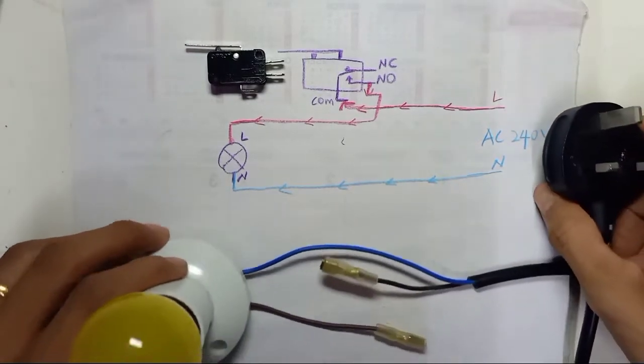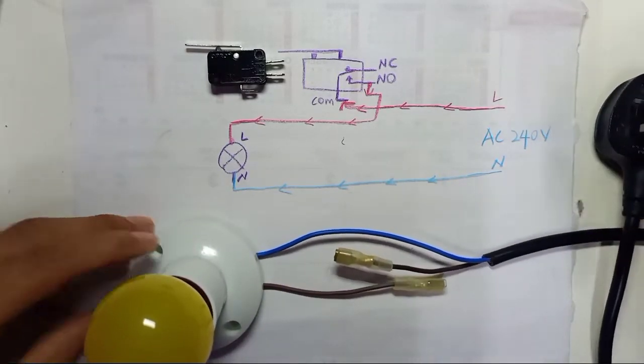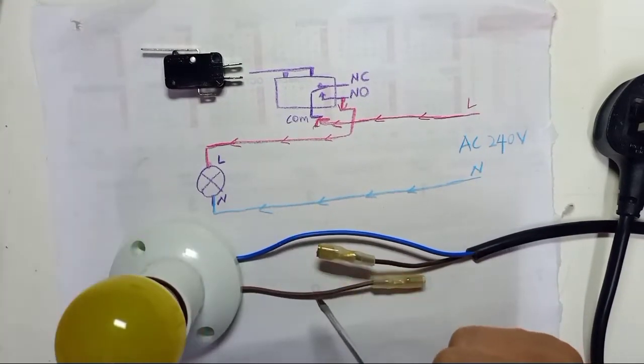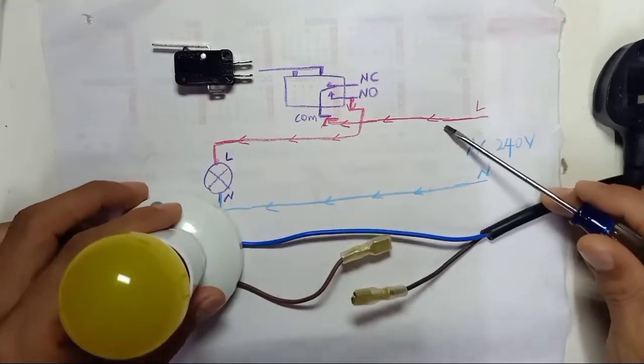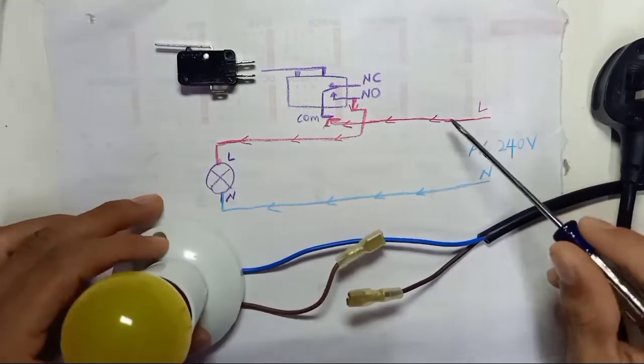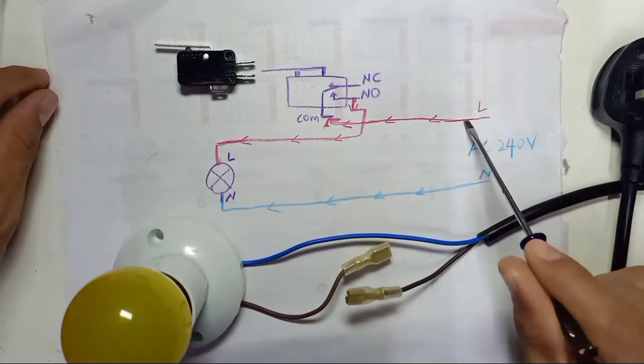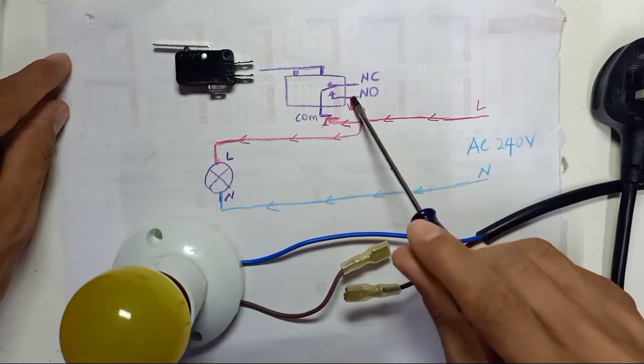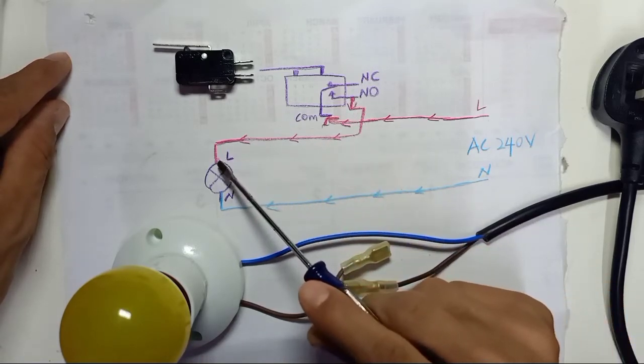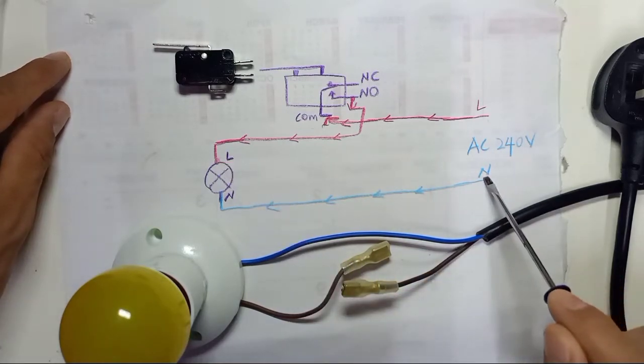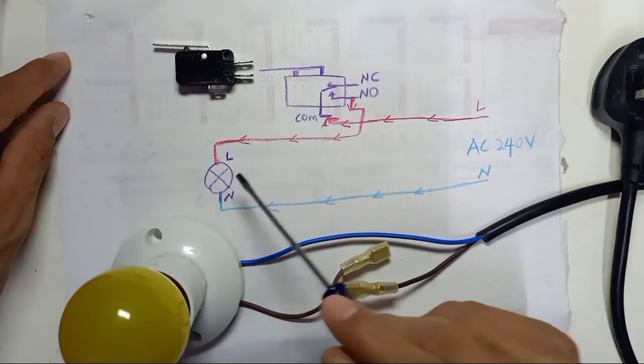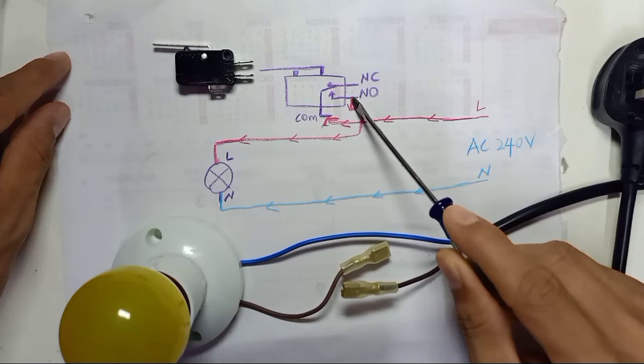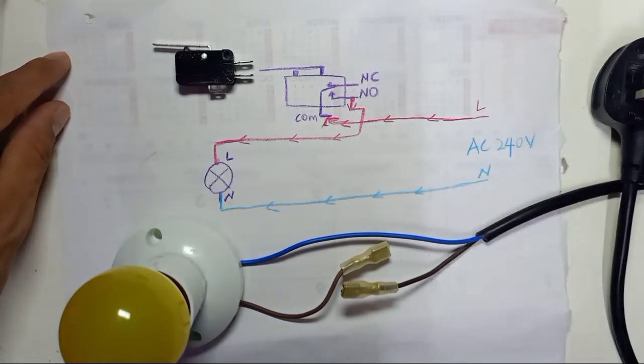Now we're going to use 240 volt AC to connect to this micro switch. You can use 240V AC or DC. In this diagram, the live wire comes to common and comes out from normally open, connecting to the lamp. The neutral wire from the power source connects directly to the lamp. If you want normally closed, just switch to the normally closed terminal.